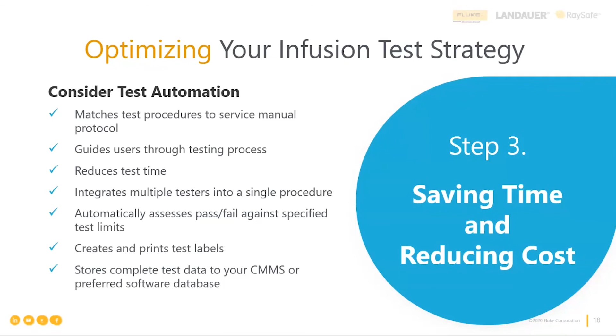So actually, I rushed a little bit and I switched to the next step already, where our recommendation to consider test automation also stems from the fact that it will save you significant time and reduce cost. And Jerry has already mentioned a few of those points, on how, first of all, you can finish your procedure and immediately report all of the data to your CMMS or any other software database of your choice. So that will save you significant time. What test automation can also do is match test procedures to service manual protocols, which already reduces time significantly. Another great thing is that you can integrate multiple testers into a single procedure for considerable time savings as well. So when you're using an electronic analyzer that has multiple channels in it, you can complete your PMs faster.